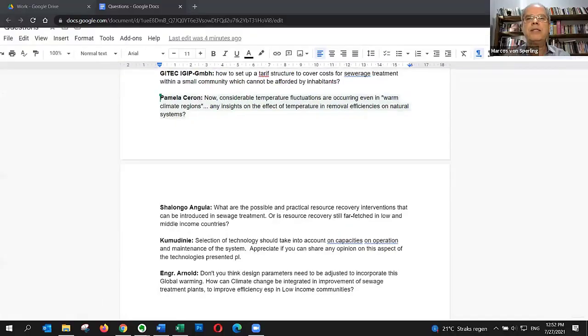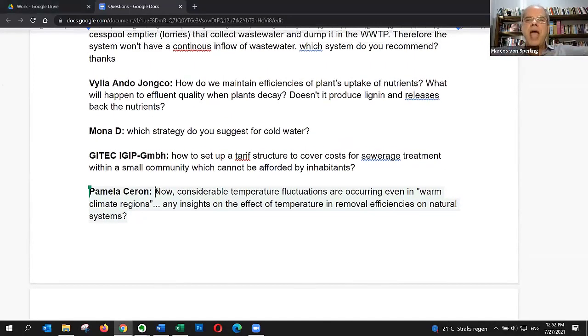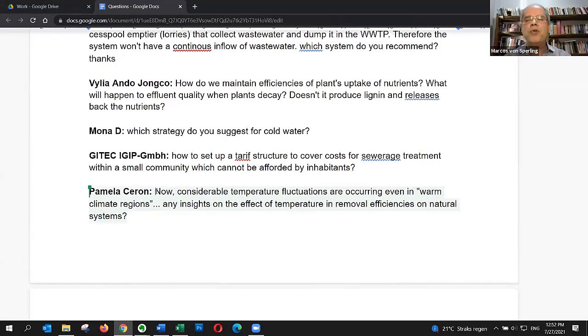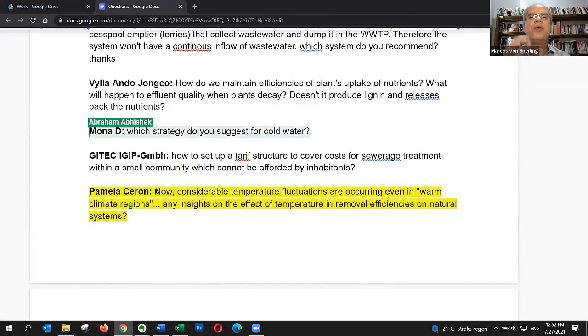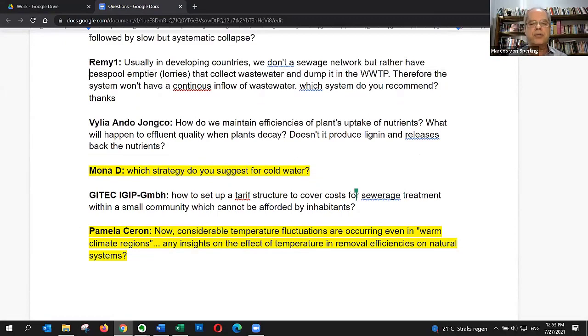They can be adopted, but they will require much larger areas for treating the same flow or load compared to warmer temperatures. For instance, facultative ponds in France use three to four times the area needed in my region. If you have consistently cold water, you could apply treatment processes that depend less on climatic conditions — typically more compact systems. Anaerobic reactors are not a good suggestion for cold climates — they depend on good climatic conditions. You still have activated sludge, or even more sophisticated things like membrane bioreactors.